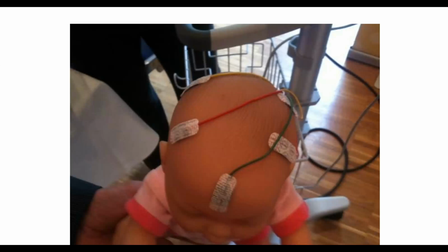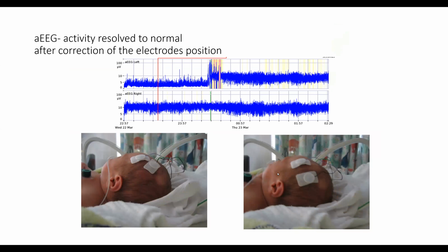Okay, so this is just an example of some really thin electrodes that we've used in some research studies. We're showing that symmetry here, so you can see the distance between them is very symmetrical, and the location on the head is very symmetrical. In this case, we just put the ground on the forehead, but the ground can go anywhere. So sensor position is very important. When you start to see asymmetry in your patterns, where one is really flattened or low voltage and the other looks kind of normal, and you wonder, is this a stroke or something else going on? Always check the sensors first.